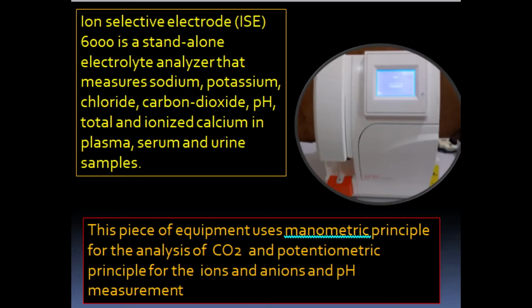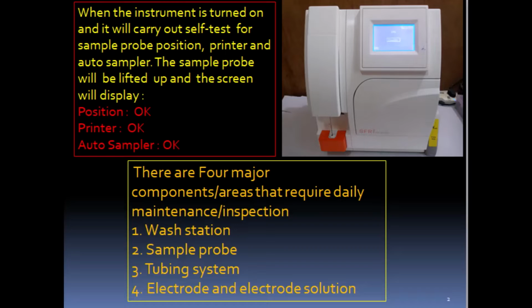Ion selective electrode 6000 is a stand-alone electrolyte analyzer that measures sodium, potassium, chloride, carbon dioxide, pH, total and ionized calcium in plasma, serum, and urine samples. This piece of equipment uses the manometric principle for the analysis of CO2 and the potentiometric principle for the ions, anions and pH measure. When the instrument is turned on, it will carry out a self-test for sample probe position, printer, and auto sampler. The sample probe will be lifted up and the screen will display position OK, printer OK, auto sampler OK.